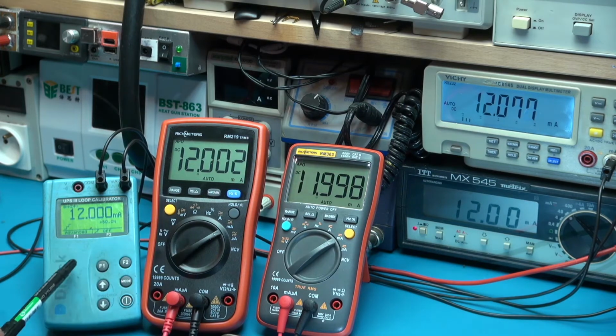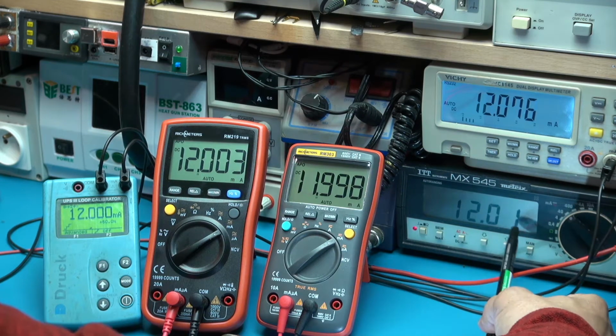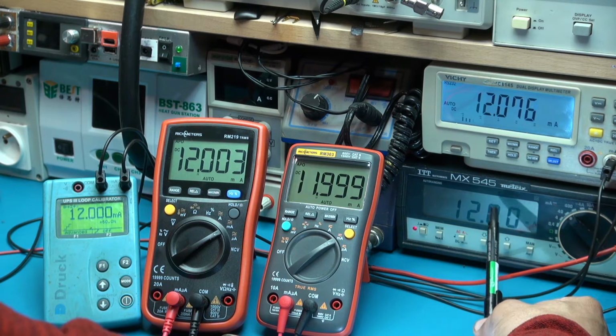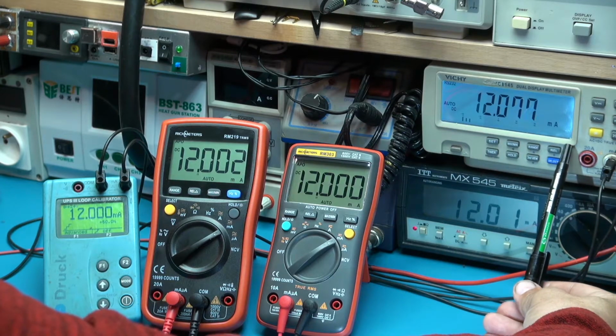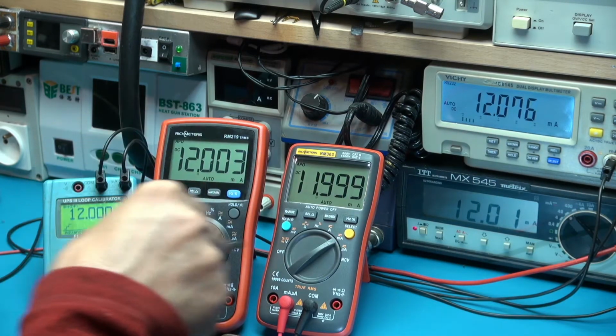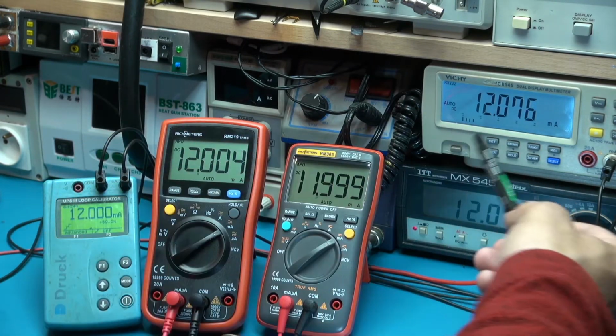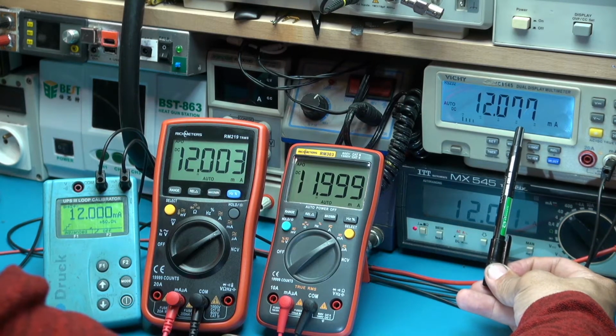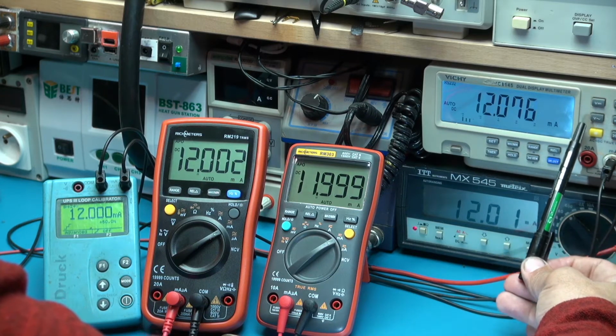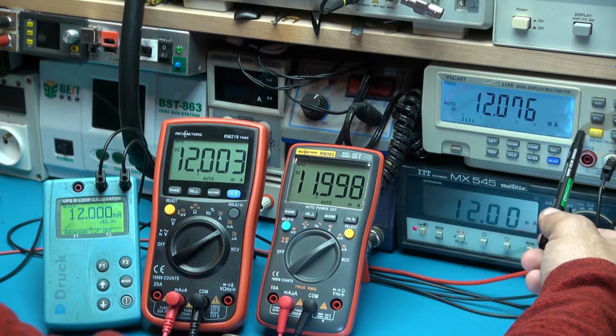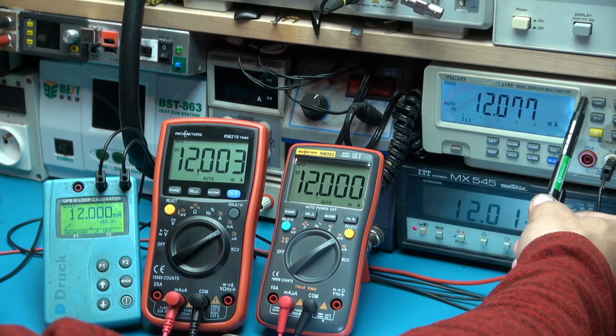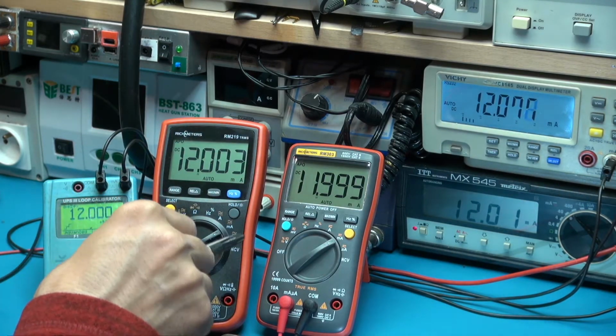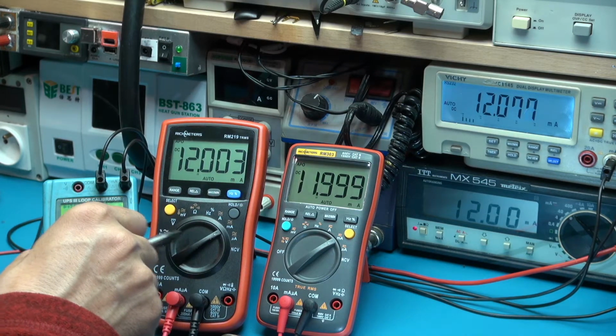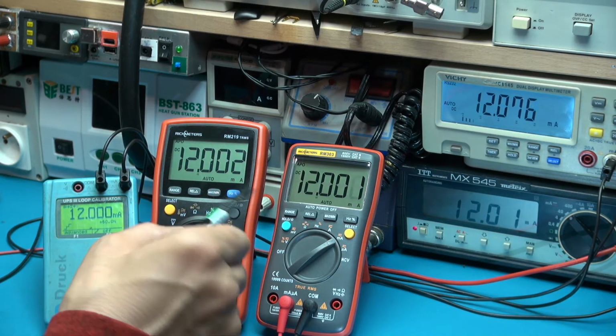and here you will have the result very close to this milliamp generator. And you can see here also a little positive offset, which is not very significant, but on this one, which is brand new and very expensive compared to those multimeters, you will have an important offset. This device costs about $150, and this device is not able to give more accuracy than those ones which cost just $20 and $23. It's very impressive.